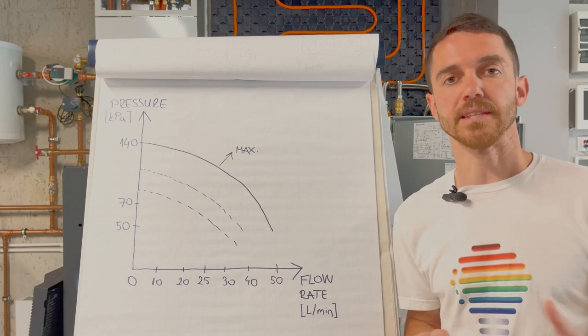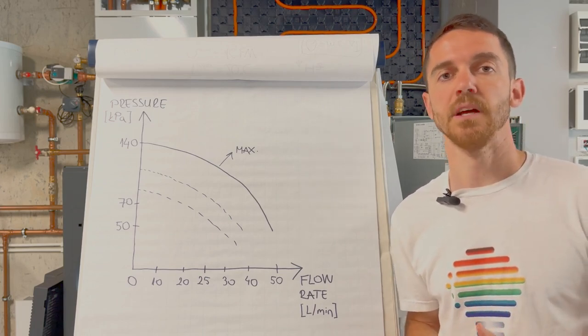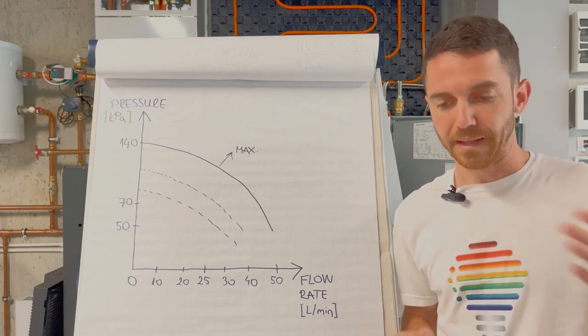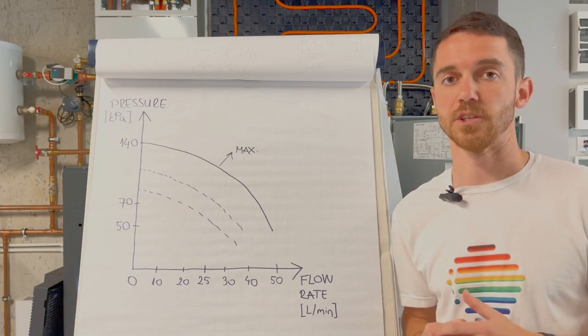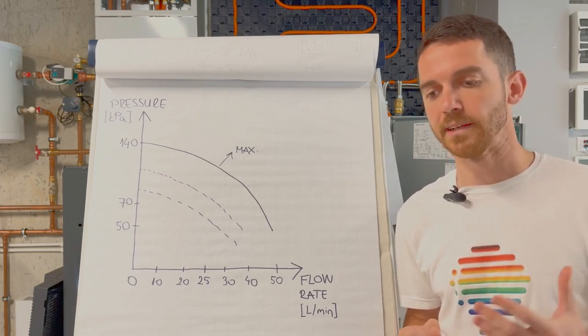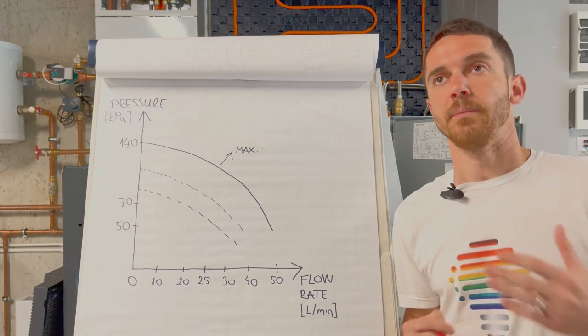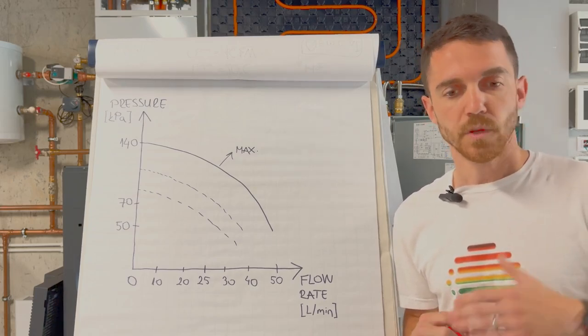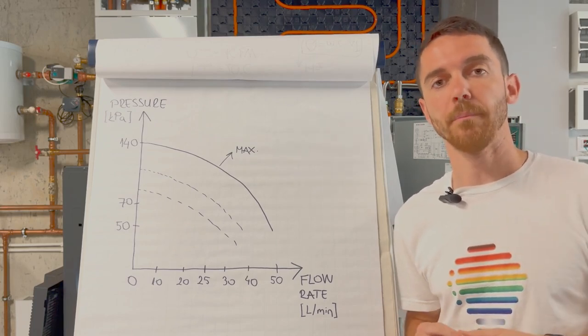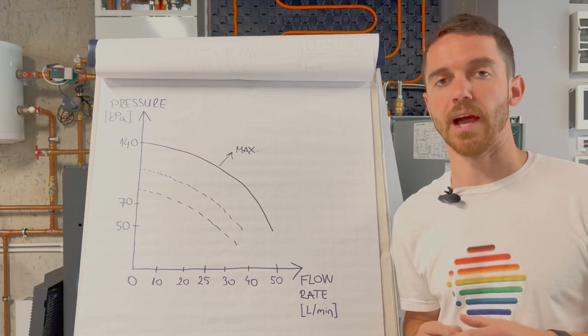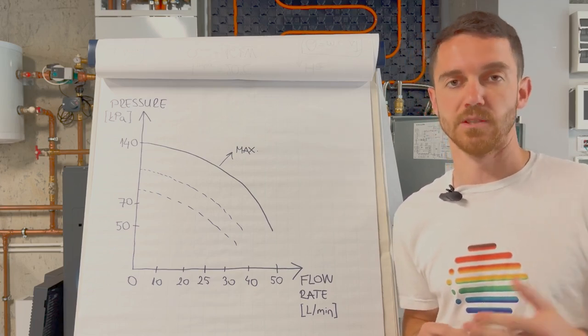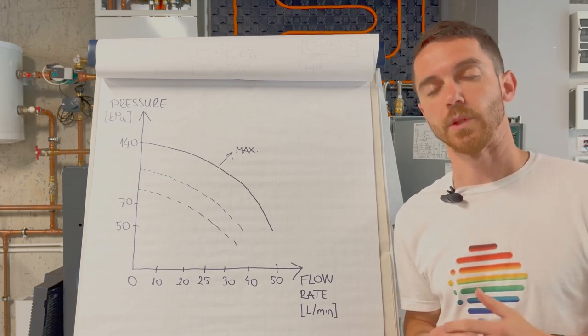But in real life, probably for 90 percent of your installations you don't need buffer. I am not talking about big systems with cascade heat pumps, with some cooling examples, with big pressure drops, but this is really small percentage. What is the main thing about buffer? The main thing is that everyone thinks that your pump, your circulator pump, is not strong enough to feed your system. But this is not true, especially with heat pumps.